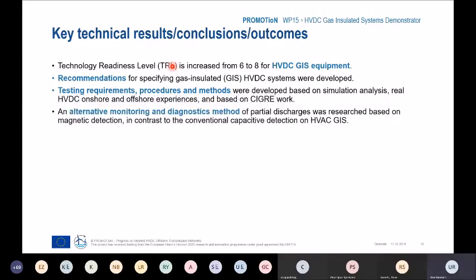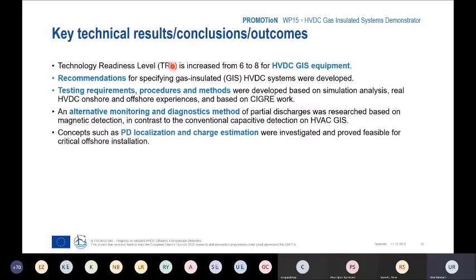At the same time, I have not spoken much about that part of our work package, but we have tested alternative monitoring and diagnostic methods, especially partial discharge measurement. The main active part was the Technical University of Delft. We have developed a magnetic kind of PD detection in contrast to the conventional capacitive detection on HVAC GIS. And by using this newly developed PD measurement, it's hopefully possible to localize the source of this partial discharge as well as a charge estimation.